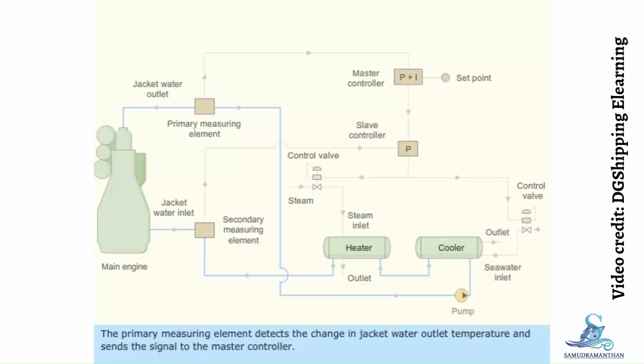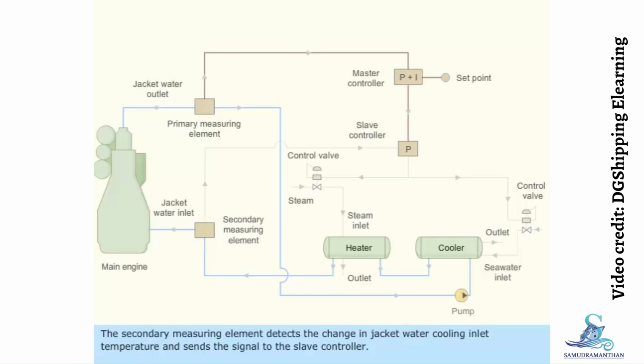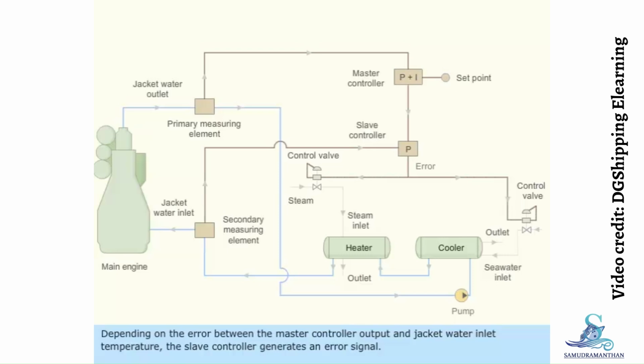The primary measuring element detects the change in jacket water outlet temperature and sends the signal to the master controller. The master controller compares the primary measured value with the set point and sends the difference value to the slave controller. The secondary measuring element detects the change in jacket water cooling inlet temperature and sends the signal to the slave controller. Depending on the error between the master controller output and jacket water inlet temperature, the slave controller generates an error signal. The error signal is fed to both the steam control valve and cooling water control valve. The dead band ensures that both the valves are not open at the same time.